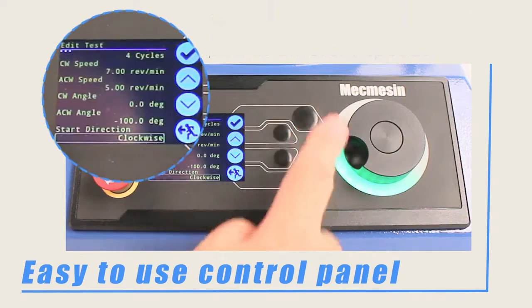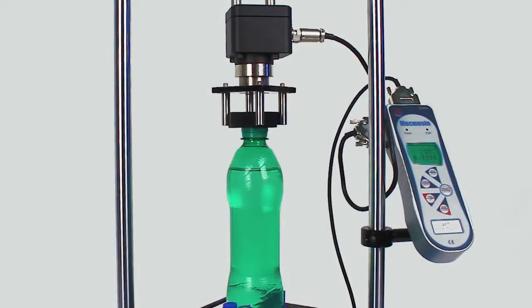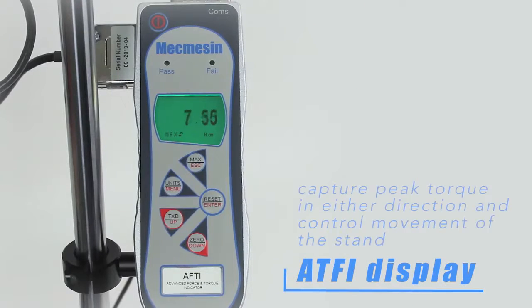There is also the provision to perform cyclic tests. The AFTI display can capture peak torque in either direction and can also control the movement of the stand, halting the test at a predefined value or if the sample breaks.